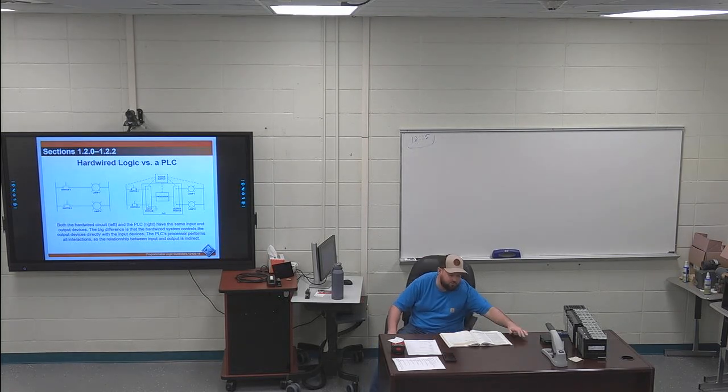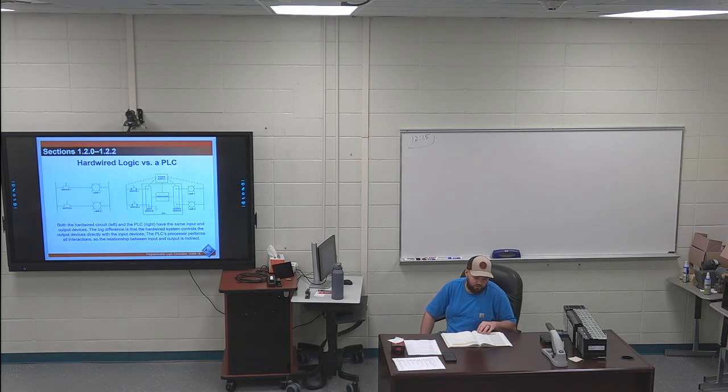Still on page 4, Figure 8 shows a hardwired vat control. This is what you would see when wiring up electric motor control. You've got a pressure switch, a temperature switch, manual override, and a motor starter. Whereas in a PLC, you're just going to see normally open and normally closed contacts, because all of those switches are digital, since they can only be on or off.